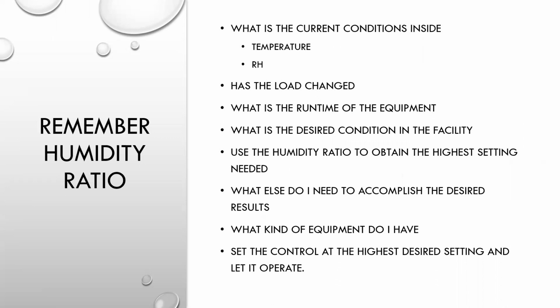Remember the humidity ratio. What I'm talking about here, and I'm going to go through this really super briefly, is that whatever the temperature is that you're desiring inside has a humidity ratio on the psychrometric chart. So if you're desiring 75 degrees, 50% RH, that means your dew point is 55 degrees. So your coil temperature has to be below 55 degrees. With that said, the adjustment of this valve is determined by the humidity ratio. So you can adjust it all the way up to the top and maintain what you're trying to do. That, again, will be gone into in much more detail in later videos.